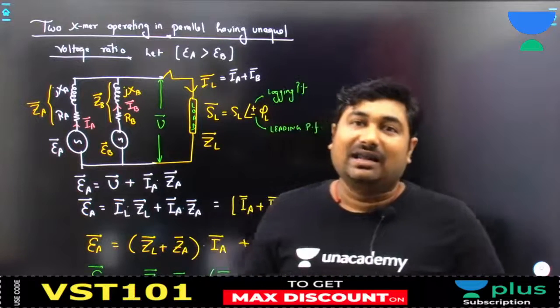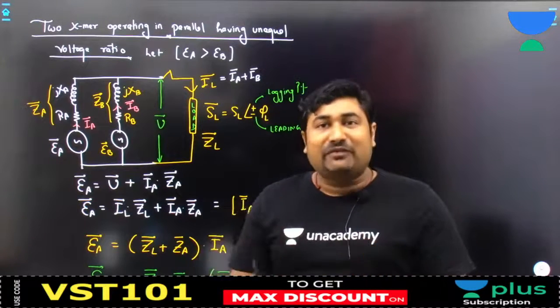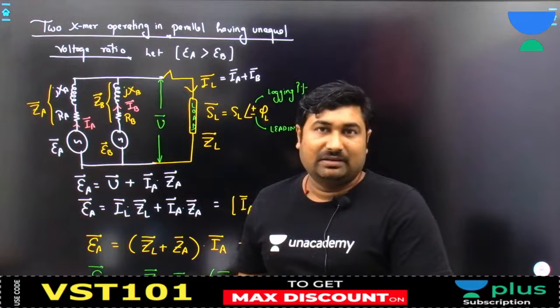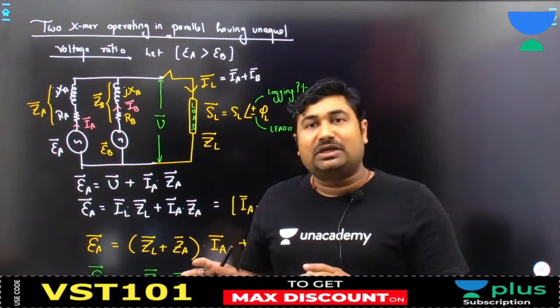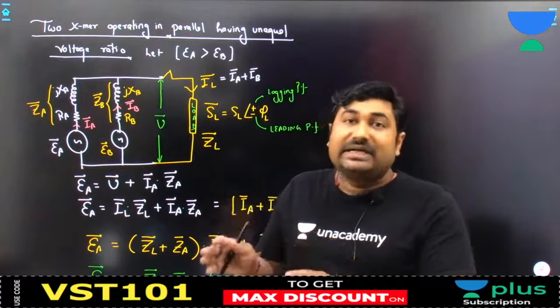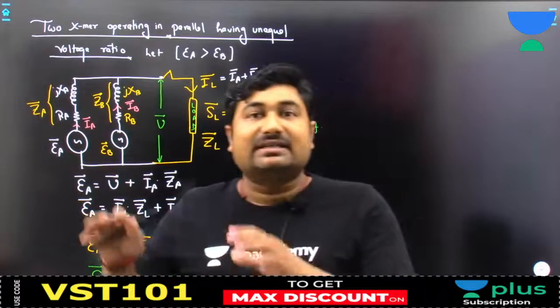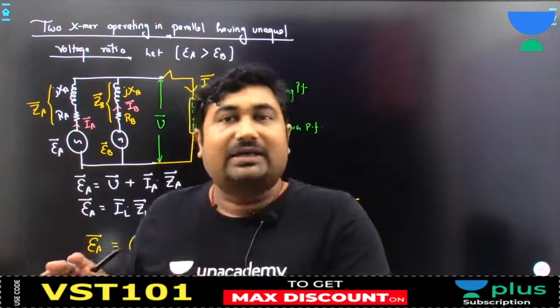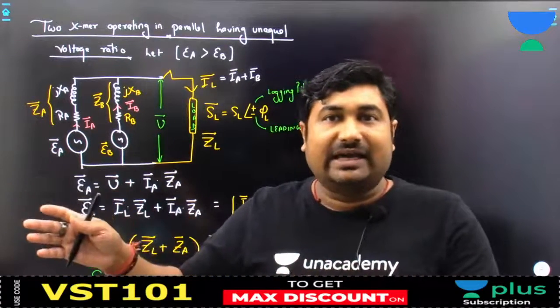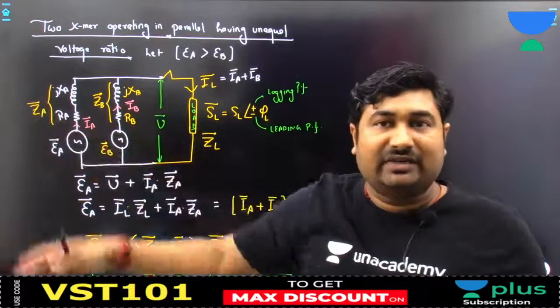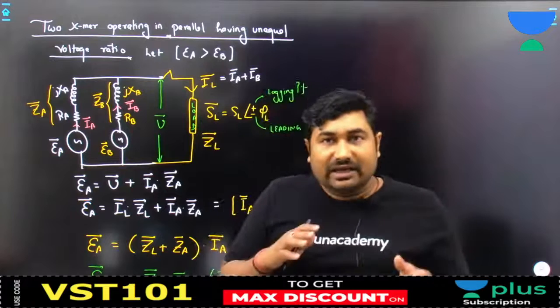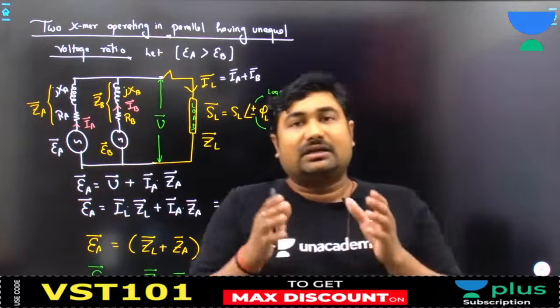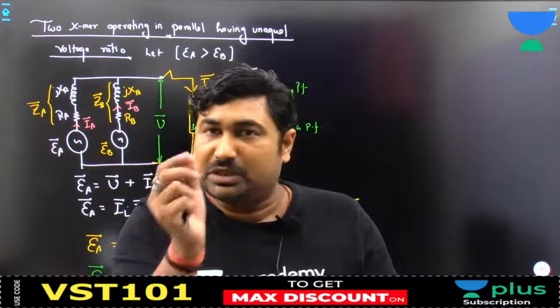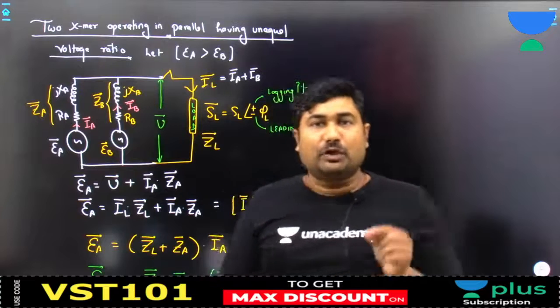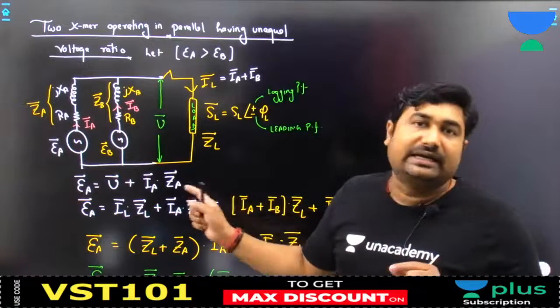Sir, unequal voltage ratio of transformers are used for which application? Parallel operation, yaar. It is very difficult to get transformers with equal voltage ratios. If you use equal voltage ratio transformers, they must be designed in the same factory, at the same time, in the same way, with the same nature of core. But if the two transformers are designed in different eras, like one designed today and one in the future after 5 years, there will definitely be a slight difference in the material, in the windings.